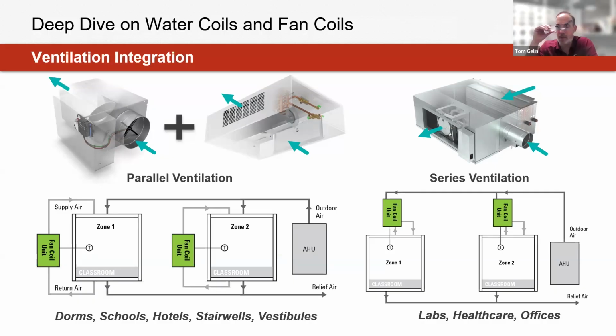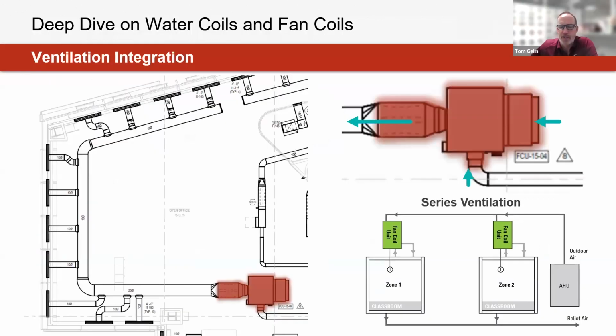So Dan's got to come up with the external static, which should include some filter loading, which would be another ballpark question mark. Depending on that, you could even see another 0.2 inches added to it for the filter. I mean, it depends on type, but that could be the additional amount you might see. You know what? One suggestion here is that filter loading is almost never in the catalog, and it probably should be. Yeah, because it's a pretty common question: well, it depends on what filter you're using. Well, let's use the one that we ship with. Yeah.